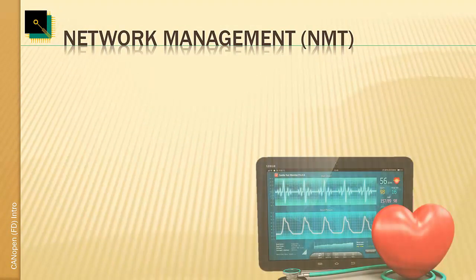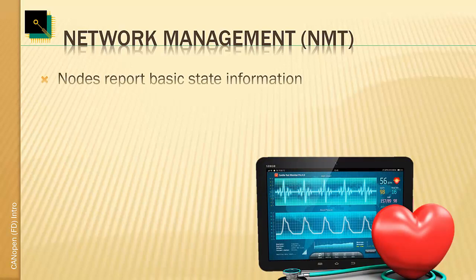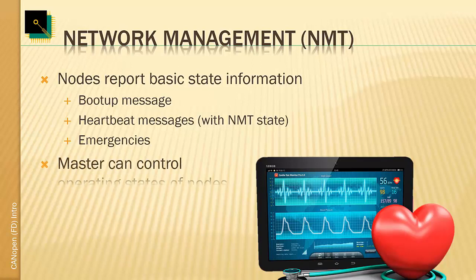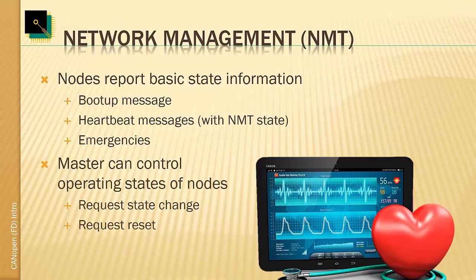The network management in CANopen gives us basic information from all nodes on the network. Every node that powers up or resets transmits a boot-up message. If configured to do so, nodes produce a cyclic heartbeat message including their basic network management state, and they can produce emergencies when they encounter an error situation. The network management master can control nodes by transmitting a single NMT master message that instructs nodes to switch their states or even do an internal reset. These NMT master messages can be broadcast to all nodes simultaneously, or the master can address individual nodes.